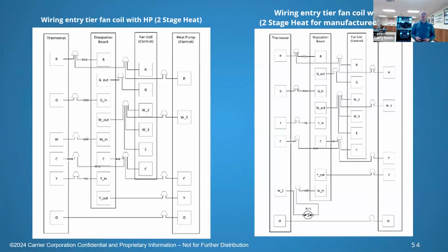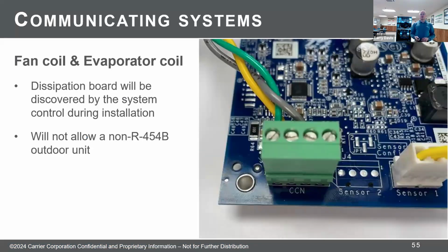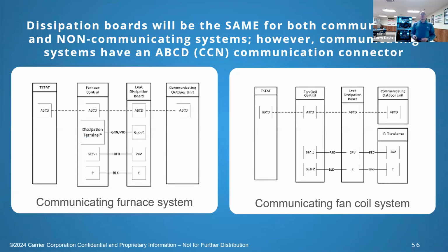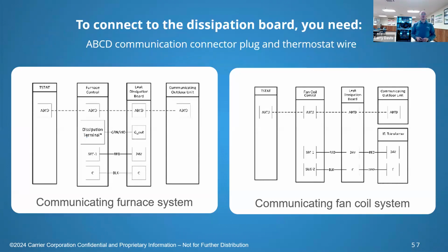For manufactured housing, the difference there is the thermostat on your electric heat. And again, I question the W2 output from the heat pump as to whether that should be landed on the W IN versus W out. Here we're just showing the green plug for the communication system, then the ABC wired to it. Shown you this before. This is where we gain time. Again, the key thing there is we still have to wire up your 24 volts from the secondary one on the furnace board.